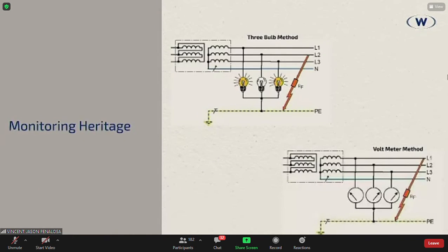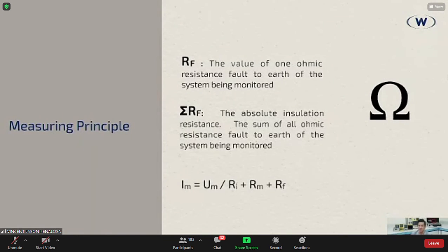And these things do not react well to that. And that's why they came up with the insulation monitoring device. Okay, so what is the measuring principle of an insulation monitoring device for an ungrounded system? So basically what happens is that it takes the value of one ohmic resistance fault to ground that's being monitored, and the absolute insulation resistance and the sum of all ohmic resistance faults to earth being monitored, and this is measured via RMS, no? So basically, it's just somehow a modified Ohm's law. Hindi pa rin naman nagbabago yun, it's still Ohm's law.